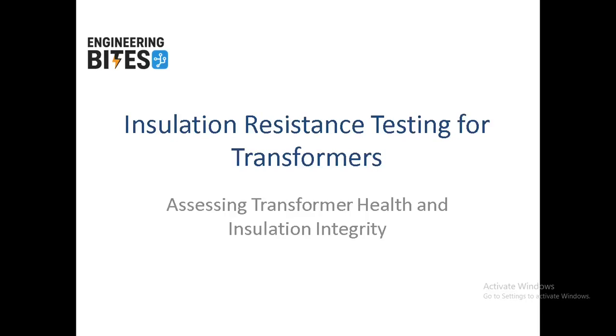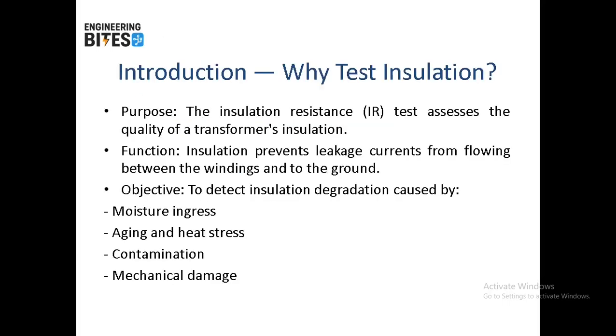Hello everyone, today we are going to talk about insulation resistance testing for transformers. The insulation resistance test assesses the quality of a transformer's insulation. The insulation prevents leakage currents from flowing between the windings and to the ground. Its objective is to detect insulation degradation, often caused by moisture ingress, aging and heat stress, contamination and mechanical damage.